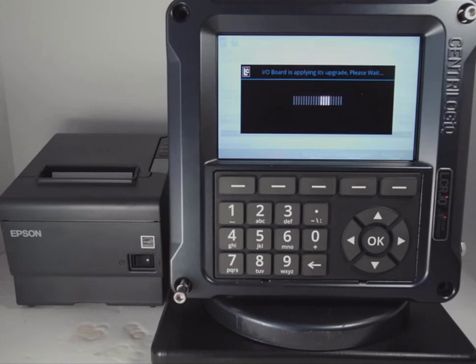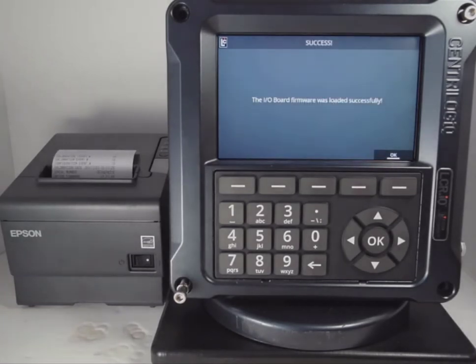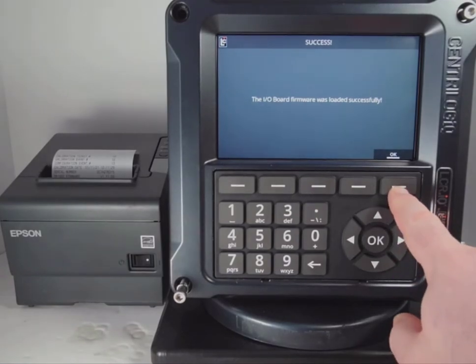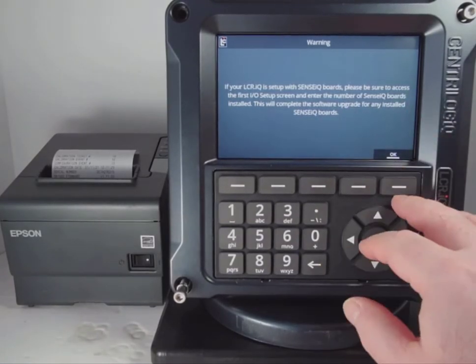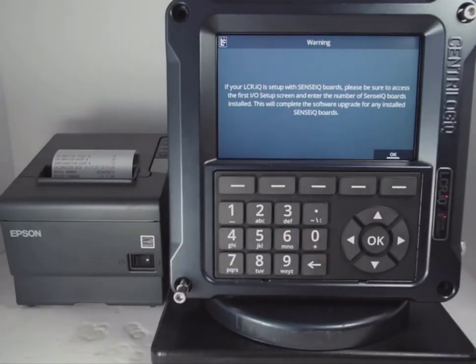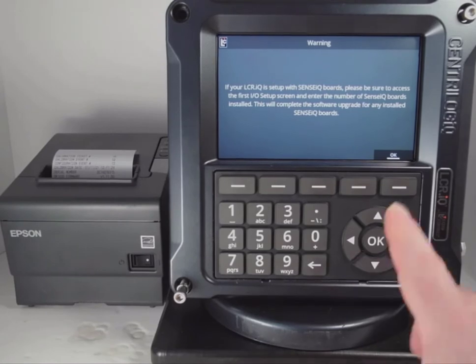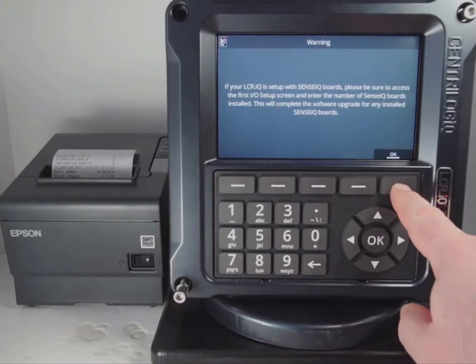Once the software is loaded, it will apply that software and complete the upgrade process. You'll see the I/O board firmware has successfully been loaded. I can press OK, and now it's telling me if I have an SenseIQ board, I should update that software as well. In this case, I don't have an SenseIQ board, so I'll just press the OK button.